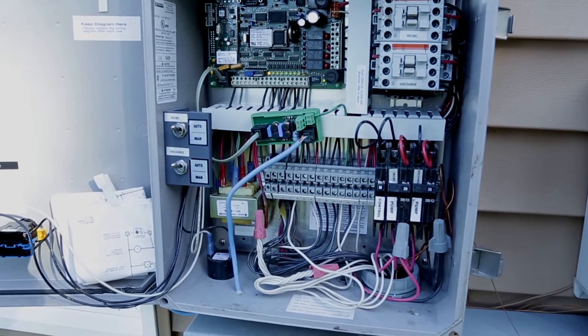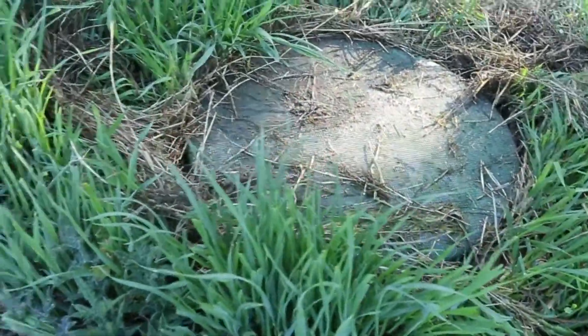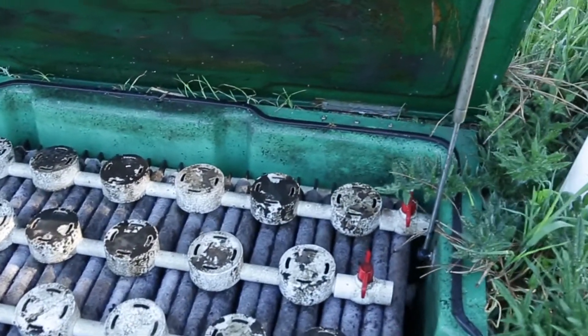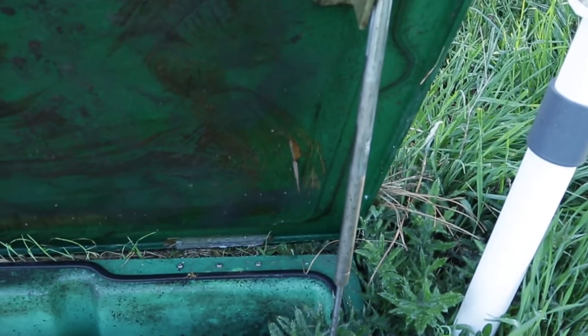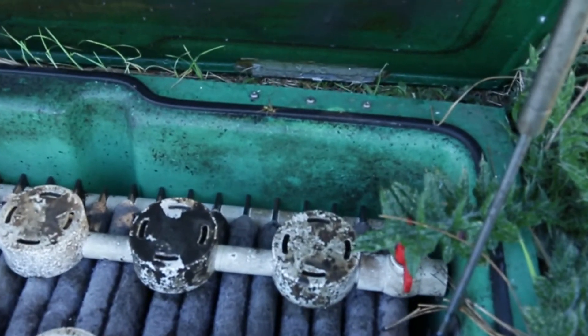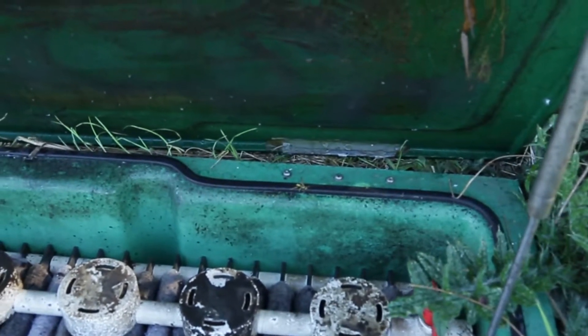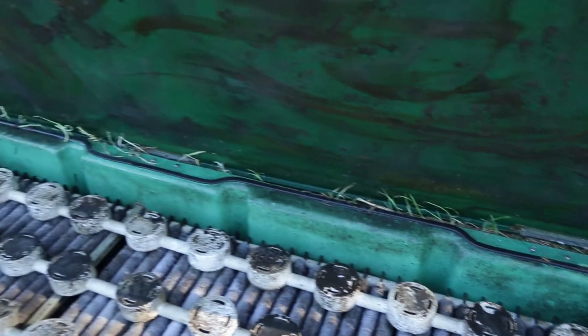Otherwise, we've got lights on on the board and power is on, so everything looks like it's functioning initially. Here's a perfect example of a system that's got quite a bit of foliage around the lids that needs to be trimmed out. We just popped the lid on this system and when we opened it, the spring assists were broken off the pod — we had to put those back on. The hinges are broken off on the back, partly because it was backfilled too high up onto the pod, and when the lid was opened it popped those hinges off.